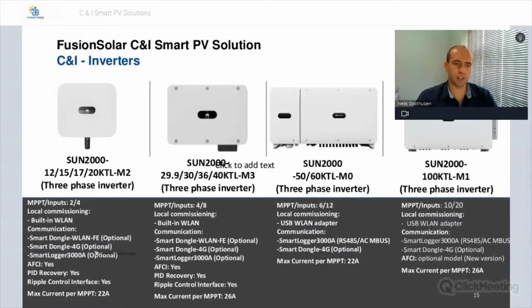The 4G is if perhaps you don't have a steady internet available, or if the installation site is in a remote location, then you will have to make use of the 4G connectivity. So as long as there's an active cell phone tower in the area and there's a cell phone signal, then all of the information can still be made available in real time. Then a third option on communication is the Smart Logger 3000A. The Smart Logger 3000A is just a more advanced version of communication. The Smart Logger supports all of these communication devices on its own. So it supports WLAN, WLAN FE, 4G, RS485, and Modbus communication as well.